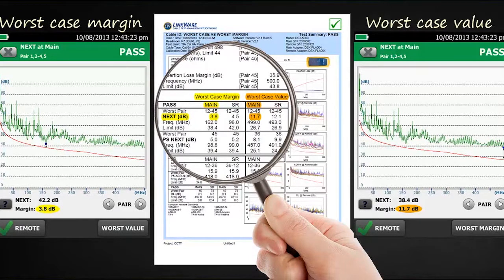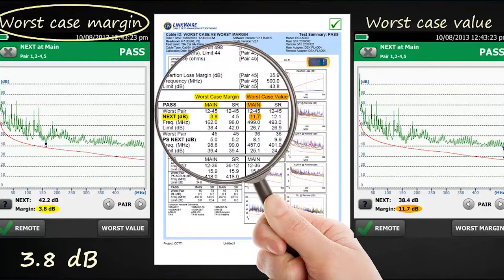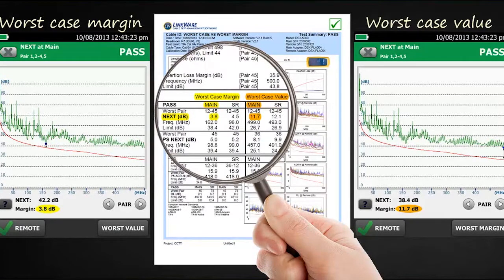How did we get into this confusing situation? It goes all the way back to 1995. Back then, there was actually not a requirement to report both — or one or the other — it was pretty much left open to the test equipment manufacturer. This became quite controversial, because if you only reported the worst-case value, the margin typically looked quite good. If you reported the worst-case margin, then the margin didn't look so good. The argument was: well, I'm only ever interested in the absolute worst value, which is the higher frequency stuff. However, the danger in doing that, as you can see in this example, is that your trace can actually be closer to the limit line than you think. The solution? Report both.